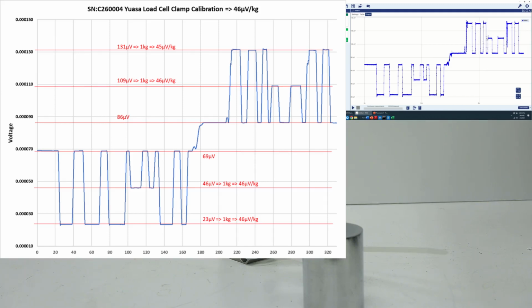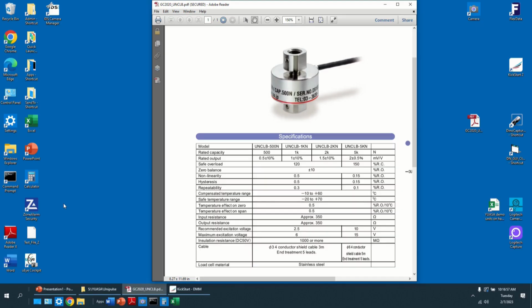I will always consider this particular load cell to have a sensitivity of 46 microvolts per kilogram. You can see why I said earlier that you probably need to measure only compression, which is easier. The offset voltage will change depending on the condition, whether it is sitting on the bench, hanging, or perhaps horizontal, as it will be when it is used on the ST when stretching a sample. That concludes that portion of the test, calibrating the load cell.